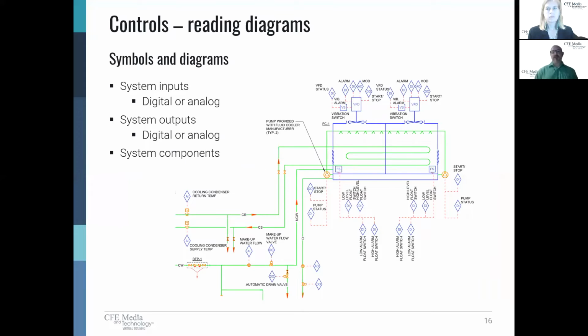Here's another example of a control diagram where we're actually defining DI as a digital input, DO as a digital output, AI as an analog input. So we have sensors and we have inputs. Now the VFDs that we're showing at the top here, those might be specified by the electrical, they might be specified by the mechanical. Regardless, that requires coordination. What do we actually want to know about those VFDs? What do we want to know about any of these other components? What if we want to start and stop this based on a fire alarm input, for example? Well, that's a contact closure. It gets back to our digital input. Engineers have to coordinate all of this to ensure that the design of the project is all-encompassing. We can't rely on the contractor or the manufacturer to figure out all of these points. The engineers have to communicate and quantify all of them.